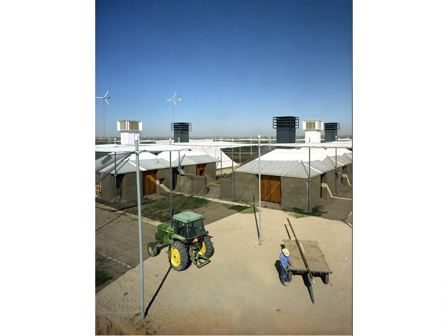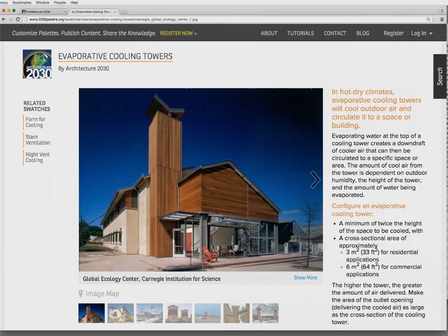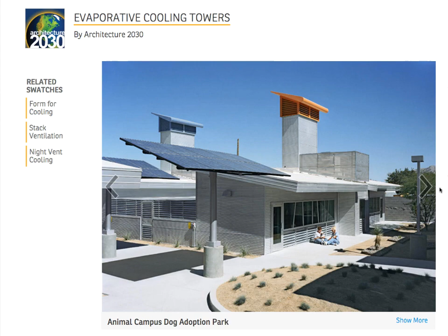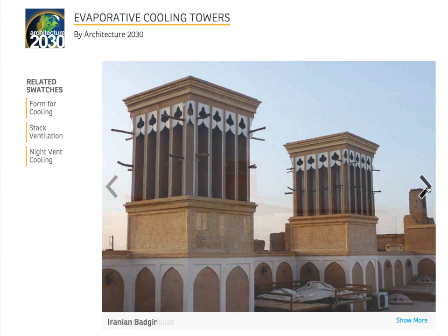So the nice thing about evaporative cooling is that it works especially in a dry climate. So it's not so great in a humid climate because you're already humid. So adding more moisture to humid air does not necessarily make it more comfortable unless you're in a really high heat gain situation. So in a hot, humid climate, we almost don't see evaporative cooling except sometimes in restaurant kitchens, sometimes in clothes washing or dry cleaning facilities, things that create a lot of internal heat gains, where being moderately warm and moist is still much more comfortable than being very moist and very hot. But most of the time we see it in a hot arid climate, so you'll see evaporative coolers all across the Southwest in their mechanical form and increasingly so in this passive downdraft form.